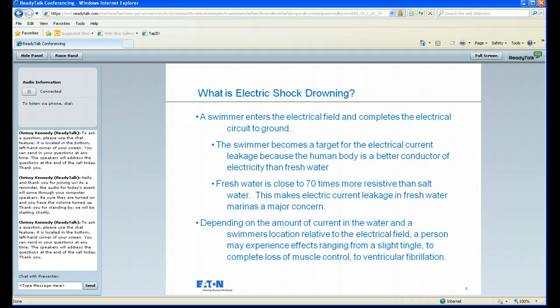It's much more prevalent in freshwater environments simply because freshwater is close to 70 times more resistant than saltwater. I saw a question a little bit earlier asking to address the differences between freshwater, saltwater, and brackish water. Simply put, the less salt you have in a location, the more dangerous currents can be within your facility, and that's simply because of how the electricity is going to cycle through the water.